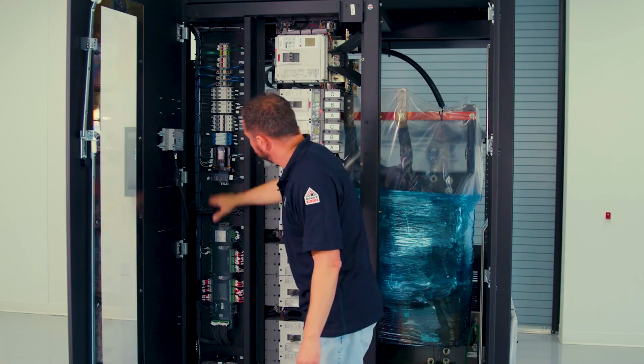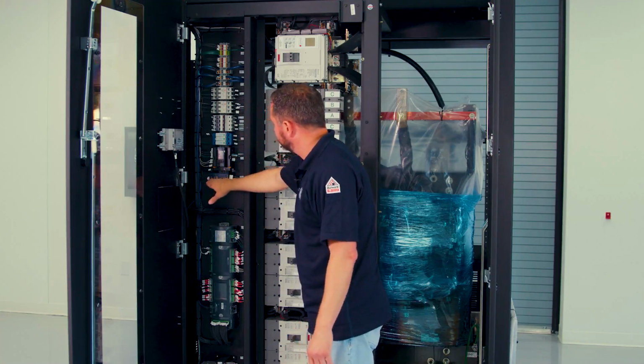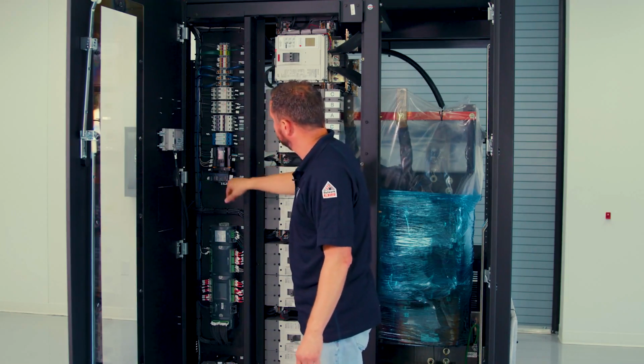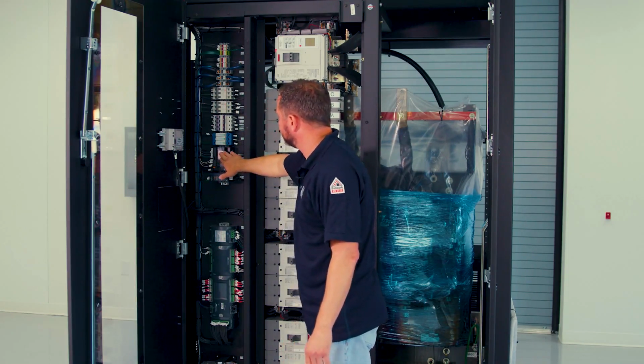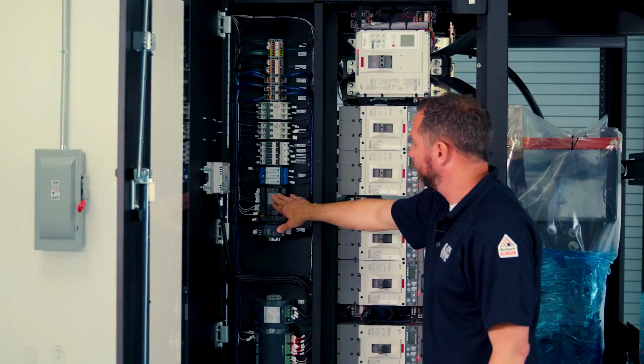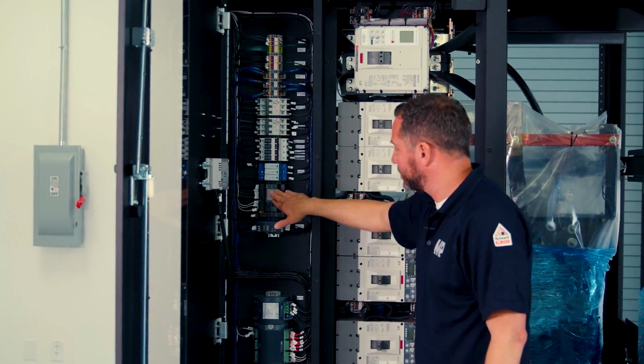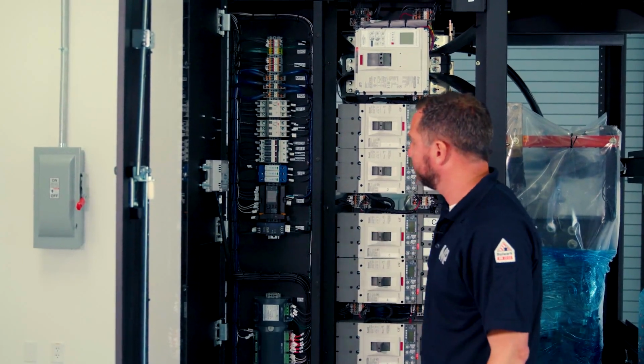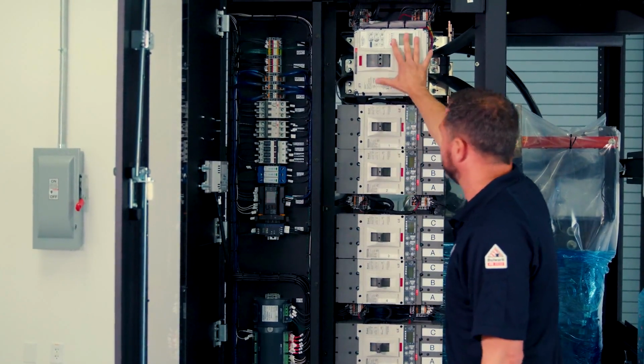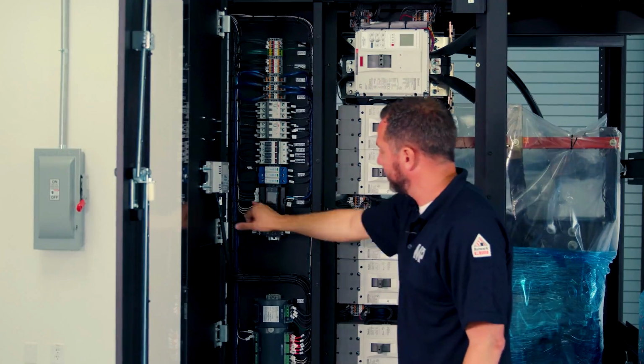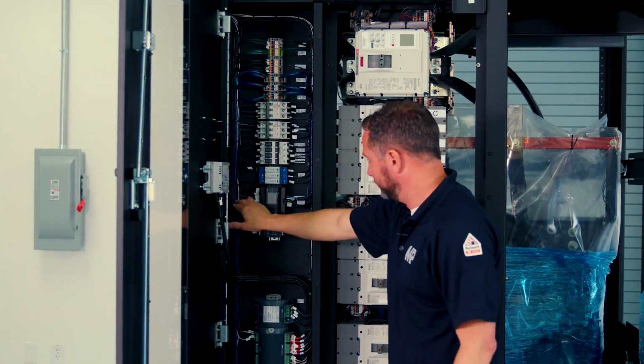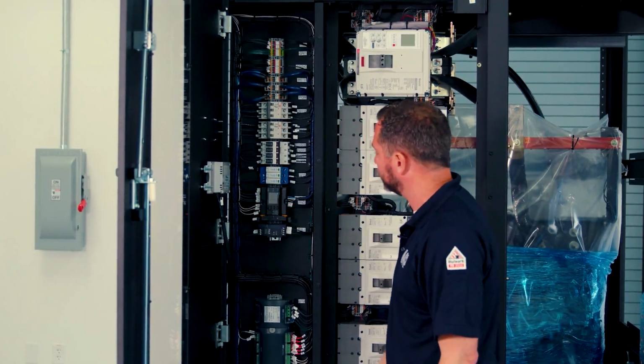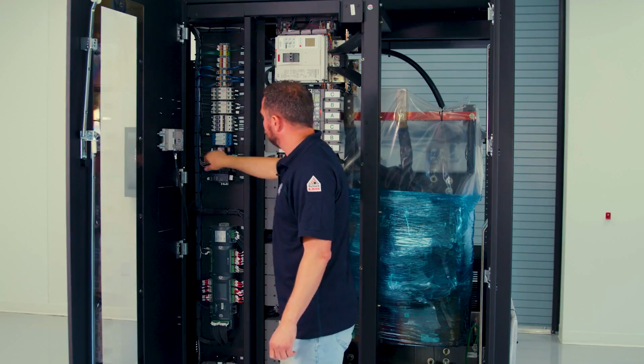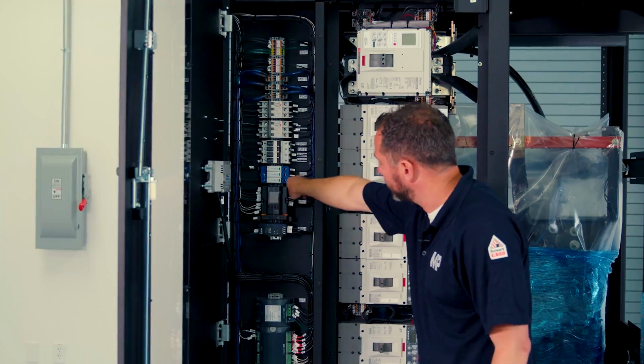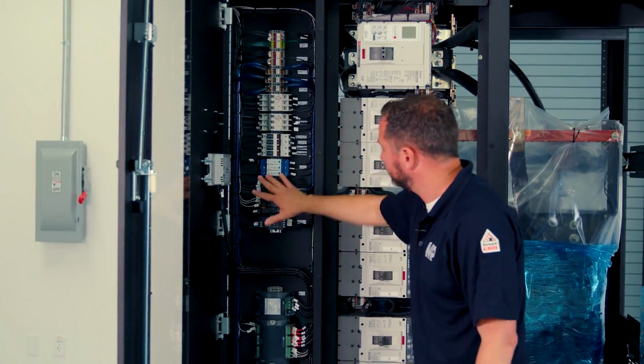So after our BFM, we have, as I said, our power supply, 120 coming in, 24 volt coming out. We have our PQM. This is on my primary side of the transformer. We also make these PDUs where this can be on the secondary side as well. But for this unit, we have our PQM that's coinciding with our main breaker. We have our main breaker CTs on the primary side reading here. We also have 480 volt coming into this PQM, and we have 120 volt actually feeding this and powering it up. And also we have our Modbus cables that communicate with our PQM, BFM, and our touch screen.